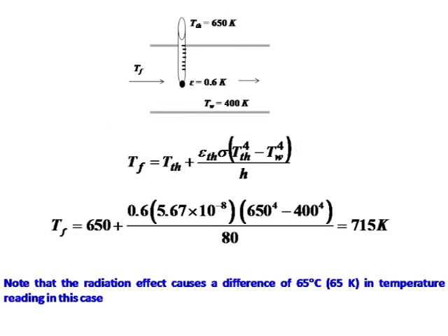So the point I want to emphasize is that not always when you insert a thermocouple or a thermometer anywhere and everywhere, it is going to measure the temperature it is intended for. That is the point we want to drive home here. If it is a low velocity flow or natural convection, most of the time measuring the temperature accurately is not an easy task. So we need to keep this in mind, because you may think that I will go ahead and try to quantify this H and this epsilon and make the correction.